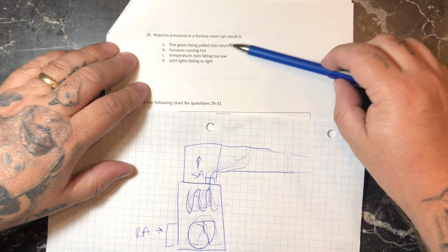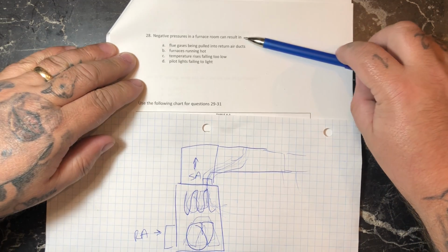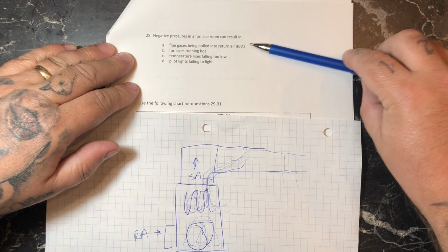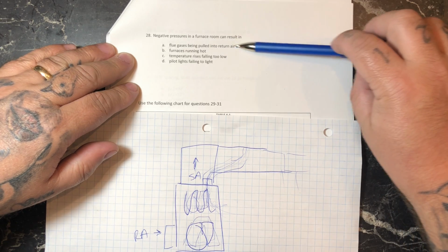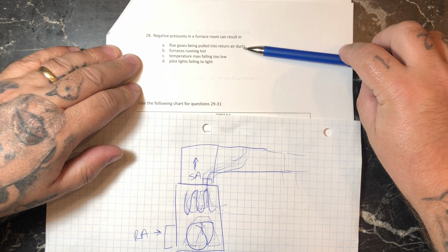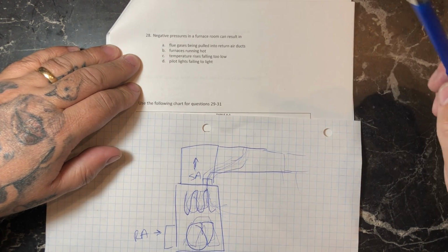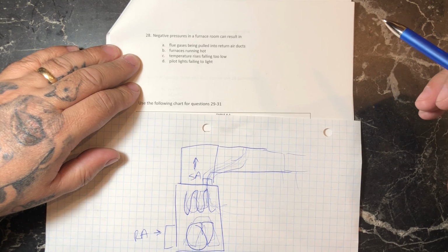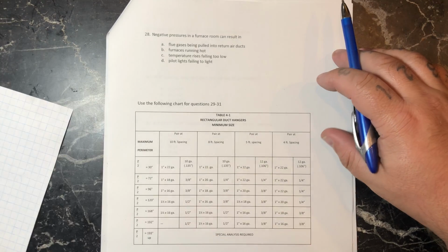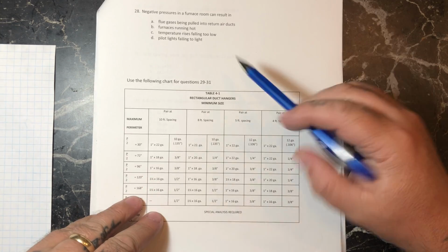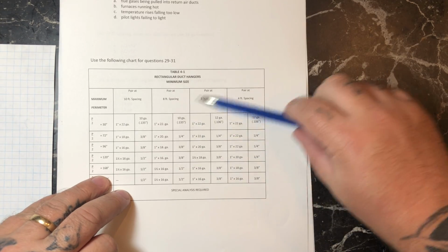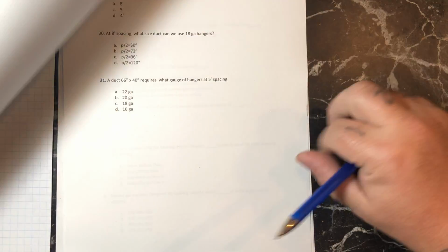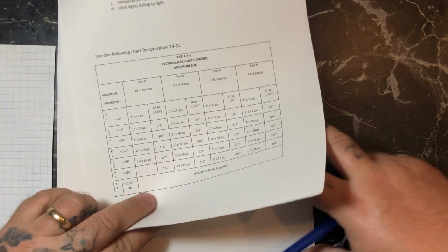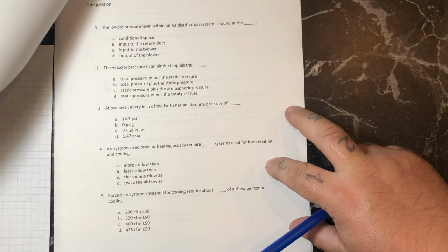But anyway, the answer on this one, negative pressure in a furnace room can result in flue gases being pulled into the return air ducts. So that's definitely the right one there. These next questions have to do with a duct hanger chart. So I think I'm actually going to skip those because they're not really applicable for you guys.